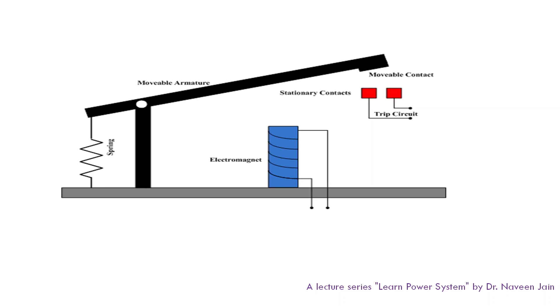Now, this diagram I explained in my last class, so I will just give you a recap. If the coil, or you can say electromagnet, is supplied by current and the current crosses the set value of the relay, this electromagnet would attract the moving armature, and the moving contact would come into physical contact with the stationary contact. So the trip circuit is activated and the signal is sent to the trip circuit. Again, the same question: why do we have a single coil and one spring here? We will discuss it in a forthcoming class, but I am giving you an opportunity to think.